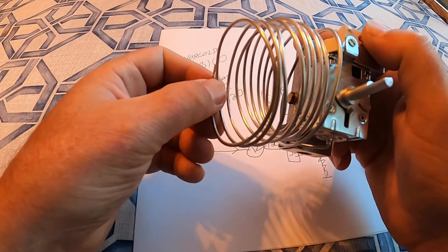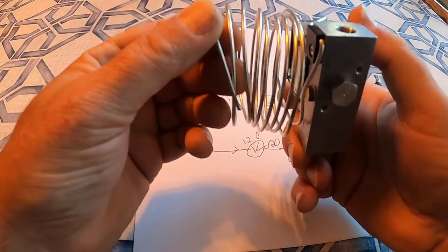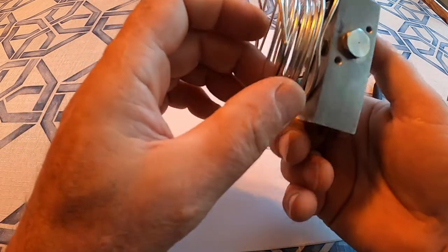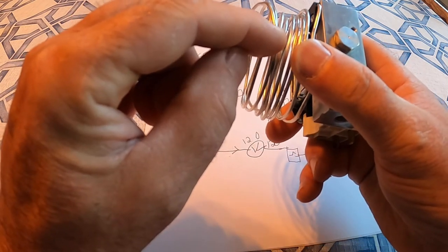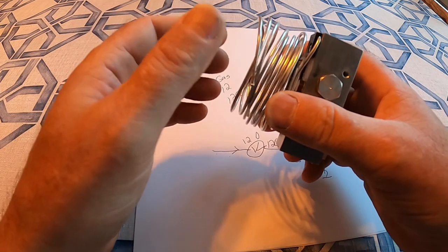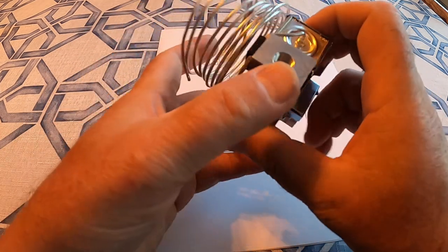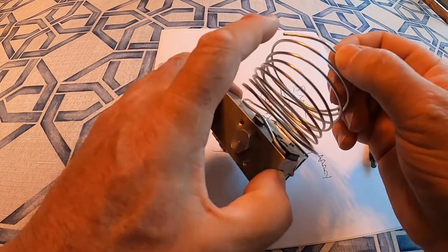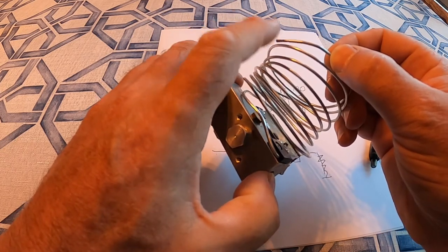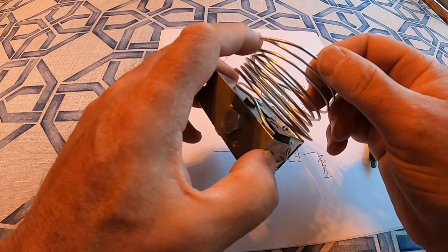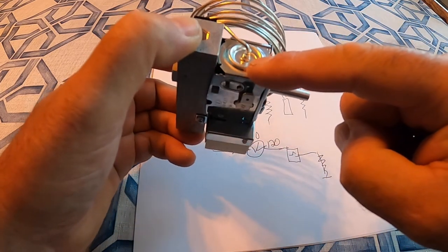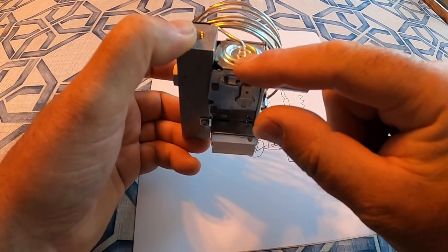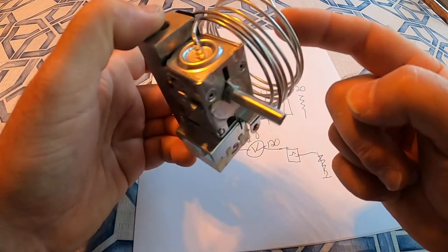This temperature sensor, what this tube is basically, it's not, it looks like a wire, but it's not. It's a hollow tube and it's full of liquid. And this hollow tube is sealed at the end. And when liquids get cold, they shrink. When liquids get hot, they expand. And so this liquid, this is basically a sensor. The end of this goes down in your, against the cooling fins. And when that cooling fin gets cool enough, the liquid in here shrinks and there's a little diaphragm here and it moves this diaphragm in and out, depending on the temperature of the end of this probe.